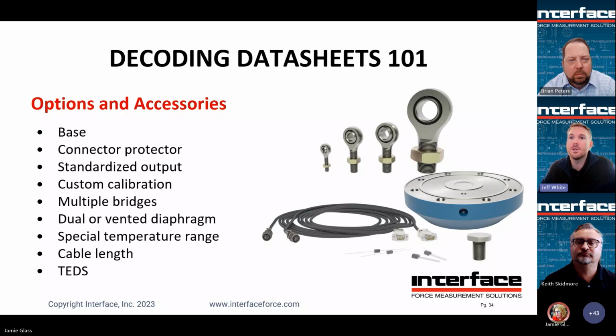Custom calibrations. Typically, calibration is 5 points up, 1 point down. On some other models, it might just be 0 and full scale. While this is fine for most applications, we're happy to focus in on your area of interest. By doing this, we can ignore some of the errors that are taken into consideration when coming up with an uncertainty budget.